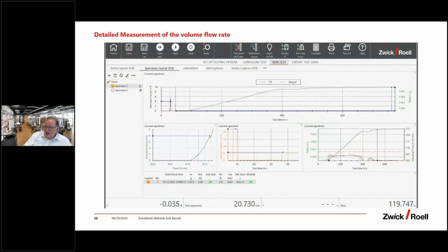And at the end, with these OBDS, to finalize it, we have seen in the autoinjector, perhaps you're measuring a volume, weight on the dose at the end. And here we are normally looking more for the injection times so long, and therefore controlling the flow rate is critical to the success of the testing. And we have to see there are constant flow rates.